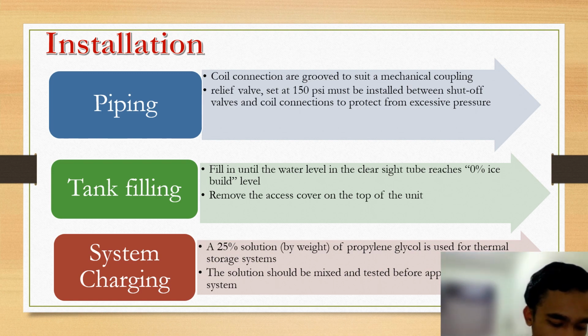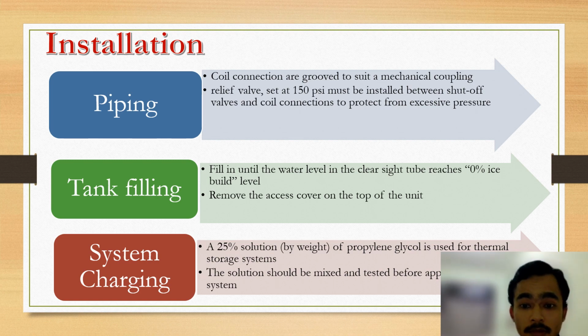So for the next part is tank filling. Firstly, we must remove the access cover on the top of the unit and then fill in the water until it reaches 0% ice build level, and this is recommended by the manufacturer. So for the third part is system charging. A 25% solution of propylene glycol is used for thermal storage systems, and the solution should be mixed and tested before applying it into the system.